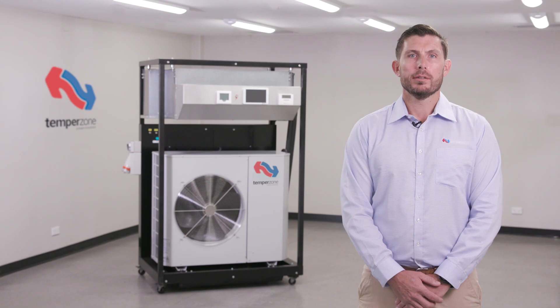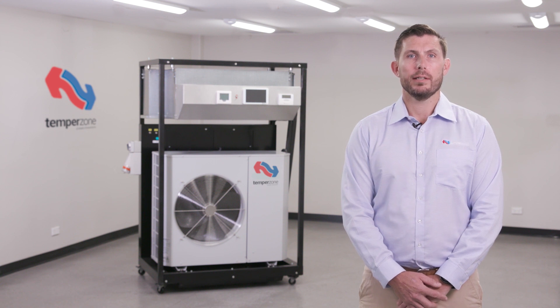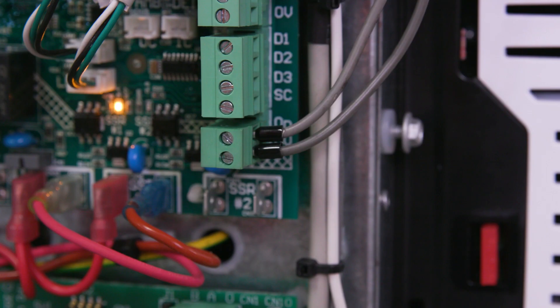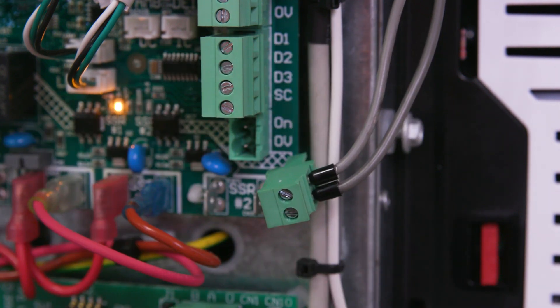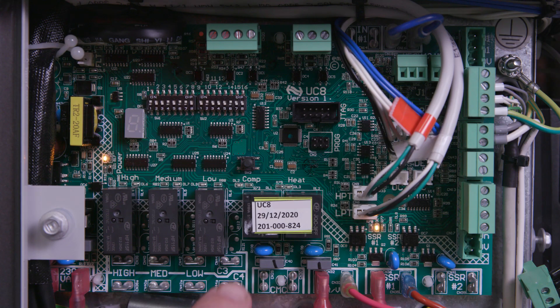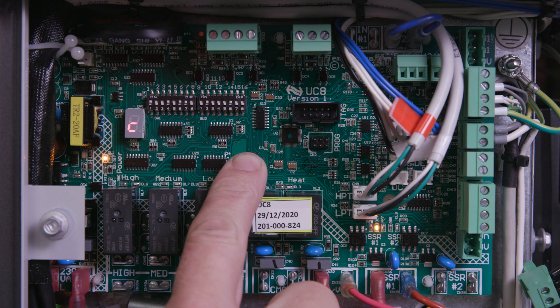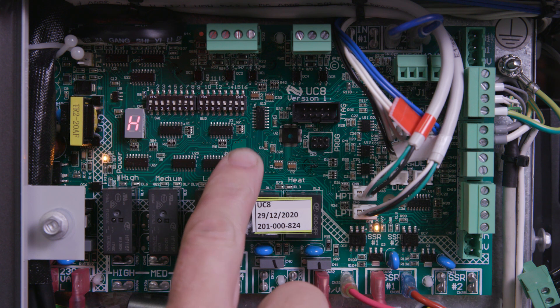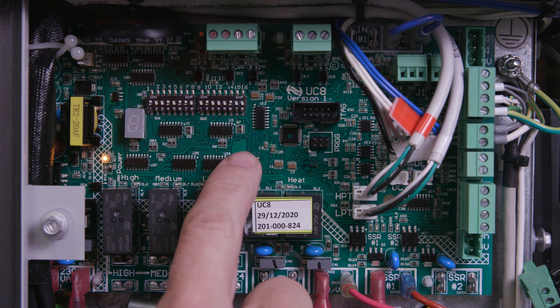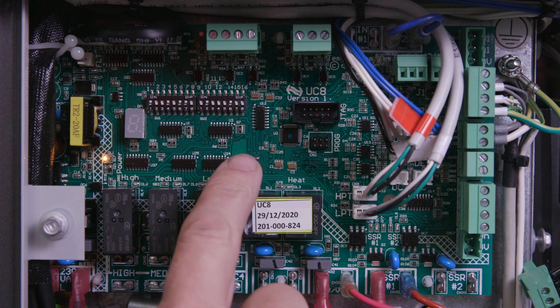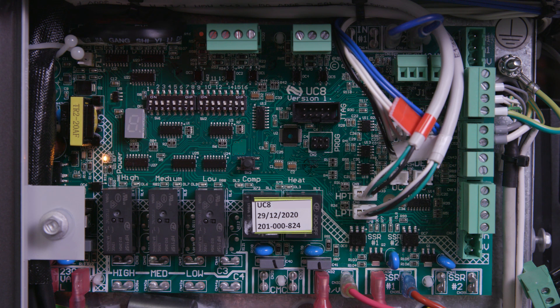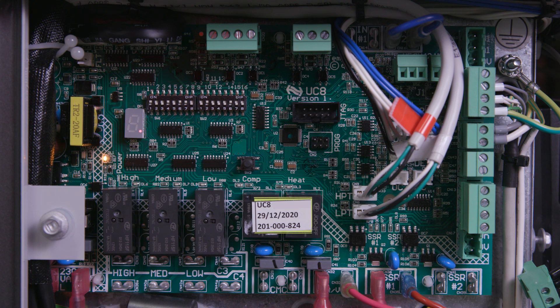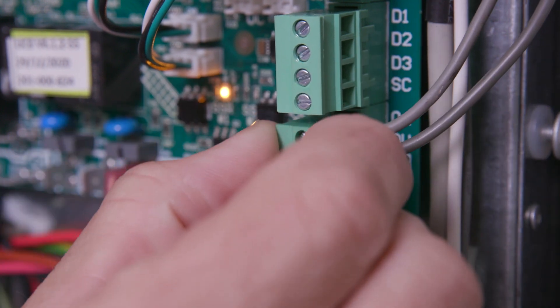To access special modes the compressor cannot be operational. To stop the compressor or prevent the thermostat signal starting the compressor when navigating special modes, remove the remote on-off terminal. Press and hold the SW3 push button. A special mode will flash three times before changing to the preceding mode. Release the push button when the desired mode is reached. The UC8 will then enter the setting for the selected special mode. Single taps of the push button will adjust the desired setting of the special mode. To save changes do not touch anything. After 15 seconds the UC8 will save the changes and return to the main menu. Reinstate the remote on-off terminal when finished.